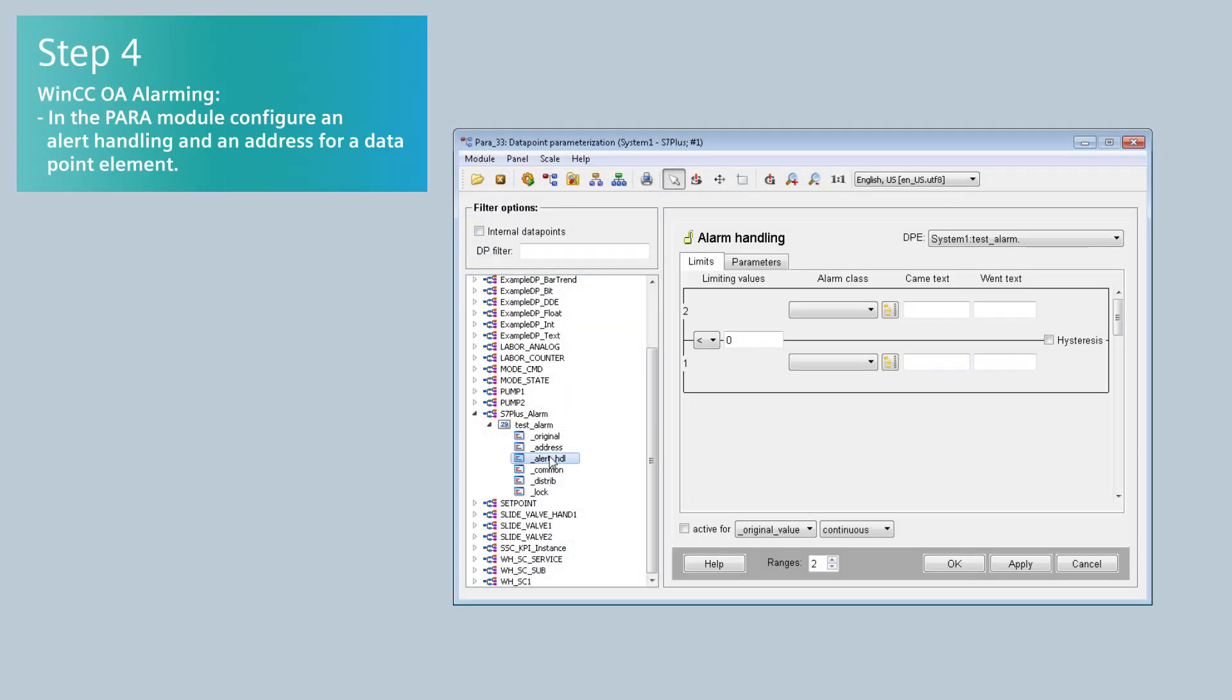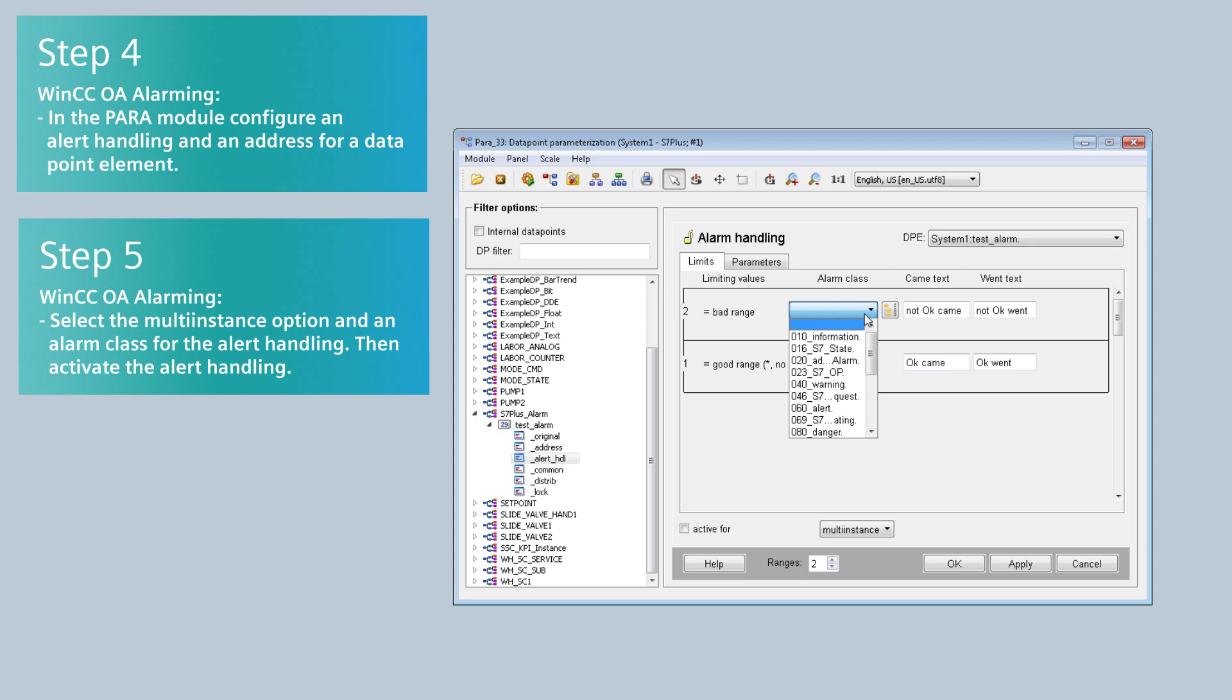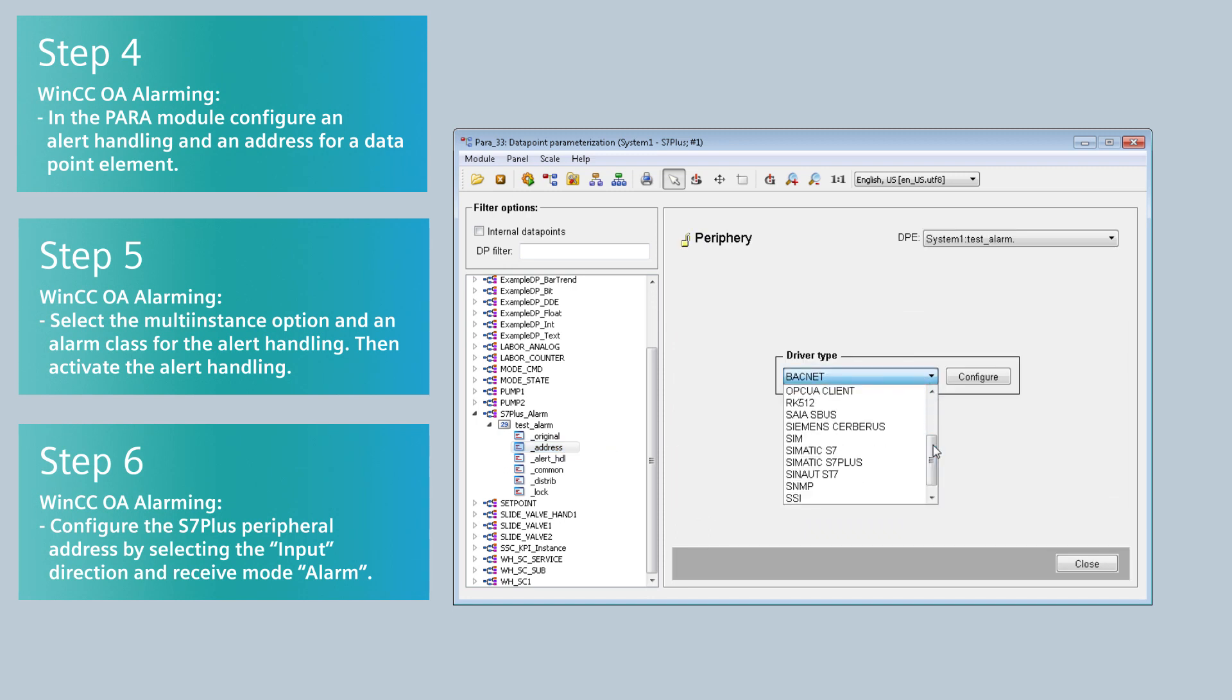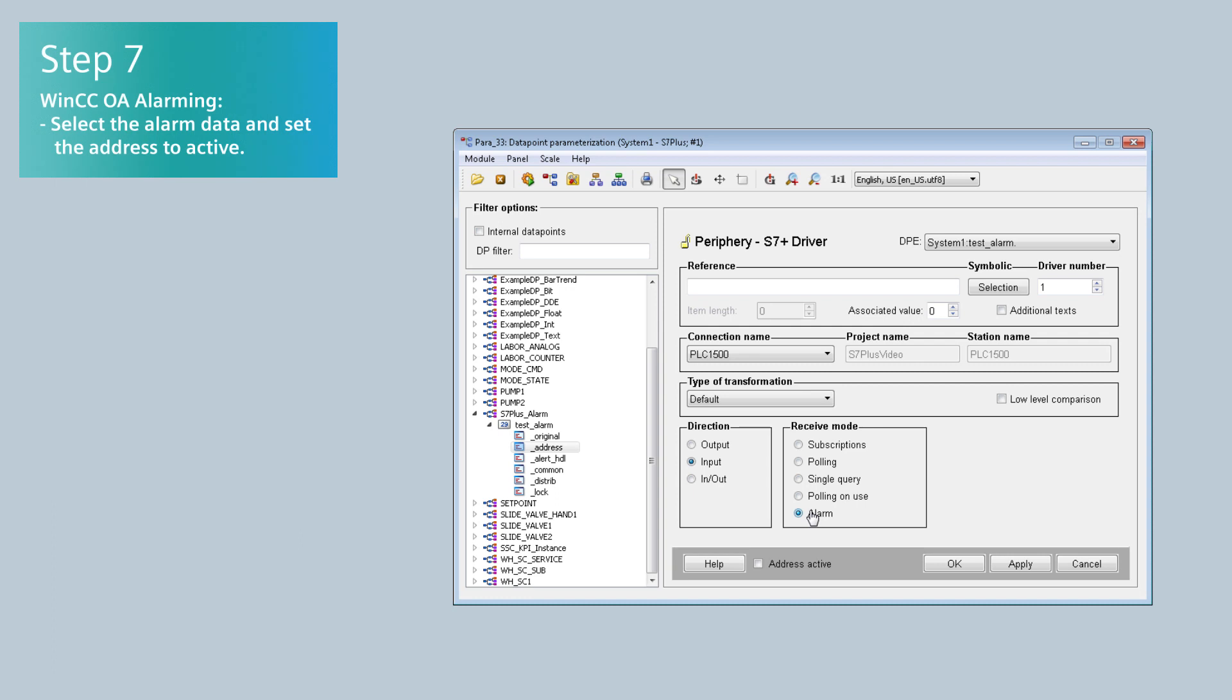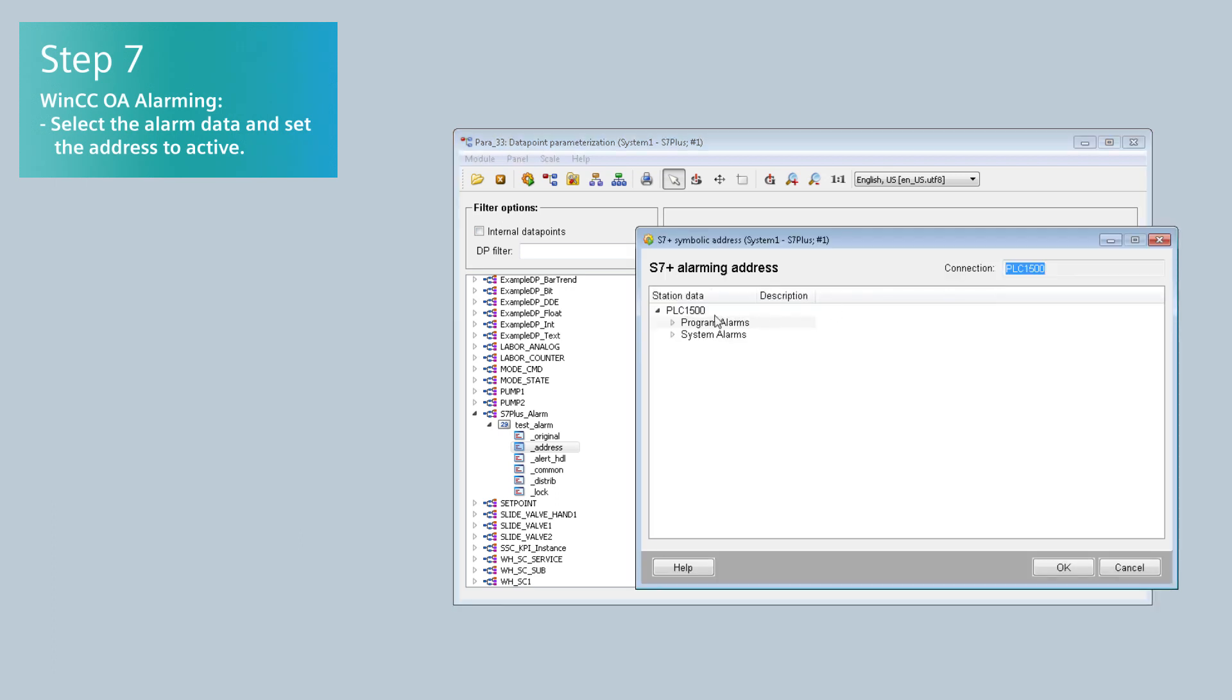In the PARA module, configure an alert handling and an address for a data point element. Select the Multi Instance option and an Alarm class for the alert handling. Then activate the alert handling. Configure the S7 Plus peripheral address by selecting the input direction and receive mode Alarm. Select the alarm data and set the address to active.